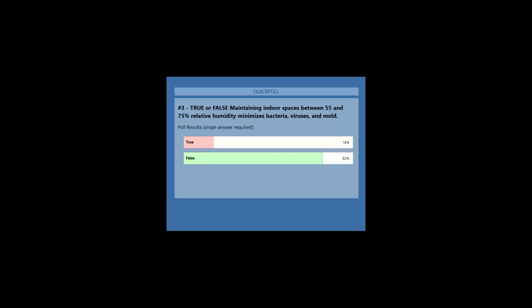If you follow ASHRAE standards, ASHRAE Standard 55 for human thermal comfort will specify that you need to keep things below 60% RH. And ASHRAE Standard 62.1, which is indoor air quality, will specify an absolute maximum of 65% relative humidity to avoid mold growth. So I definitely want to keep things under 60. With that being said, the new ASHRAE standard switched from a relative humidity recommendation to a dew point recommendation. So I'm just saying it based on the old one before somebody corrects me, which I'm sure one of you will.